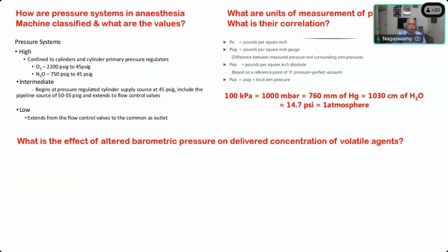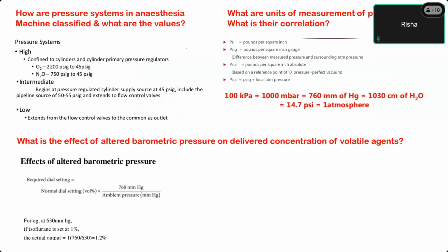What is the effect of altered barometric pressure on the delivered concentration of volatile agents? As the altitude increases, will the ambient pressure come down or go up? At high altitudes, the ambient pressure will be low, lower than sea level. When there is a lower pressure, what will happen to the output concentration? It will increase. The volume percent of the agent released from the vaporizer increases.